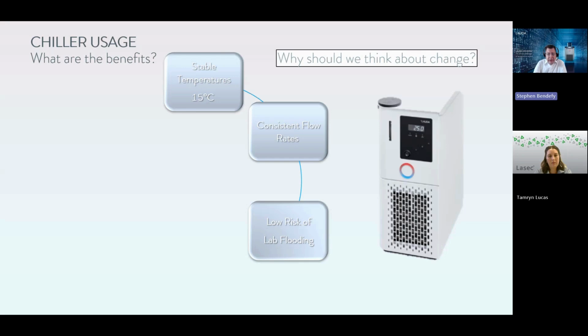There's a very low risk of flooding. We acknowledge that, yes, a pipe may come off if it's not secured properly. However, it's only the contents of the chiller that could potentially leak, not a continuous flow from a mains water supply or from a cooling tower or from a larger system. We don't need to supply a water mains input and a water drain. It's not required, as we discussed with the porta cabin laboratory approach.